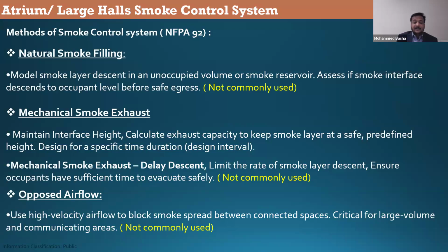Mechanical smoke exhaust delay descent. This is also not commonly used. In this case, for example, in the previous case I mentioned, maintain interface height, if you are using X capacity of fan in the second one, mechanical smoke exhaust, we will not be using X capacity, we will be using 0.5 X capacity. So we will allow the smoke to get down as time passes, so the occupants can evacuate.